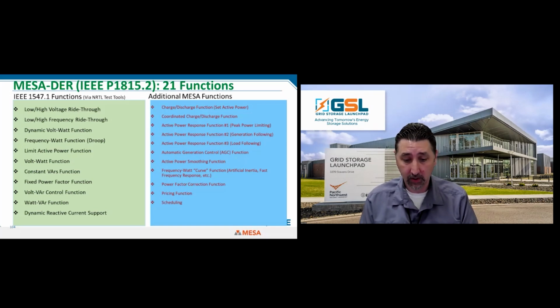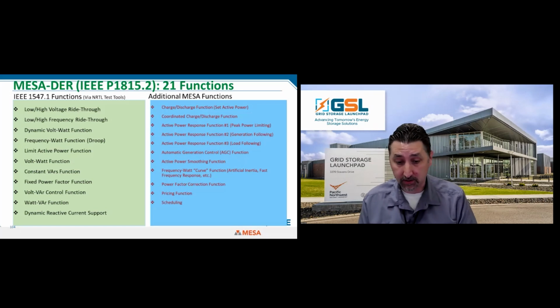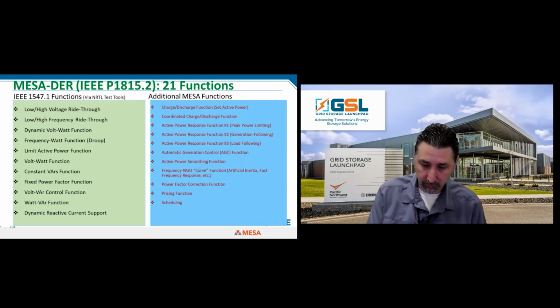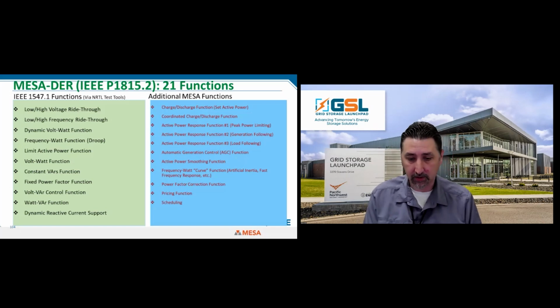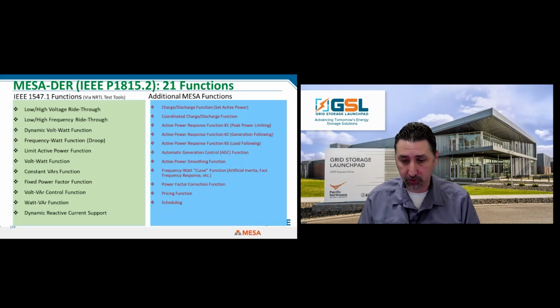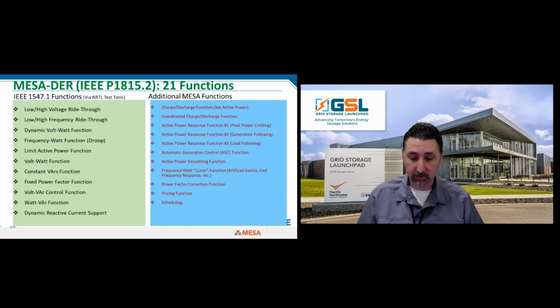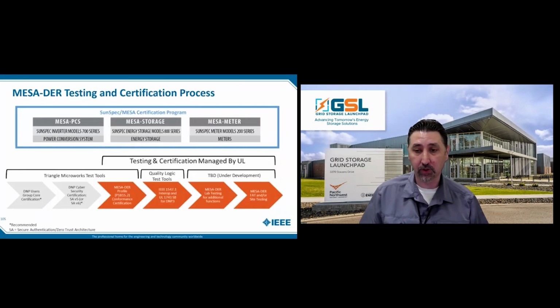Frequency-watt curves, power factor correction functions - so when power factor is off, it steers. Pricing, scheduling - scheduling isn't even included in 1547. And then there's some active power like generation following. Those things are really valuable if you're operating one of these storage systems - those are the key things you want. If your system has only been certified to 1547, you've missed all those functions on the right.